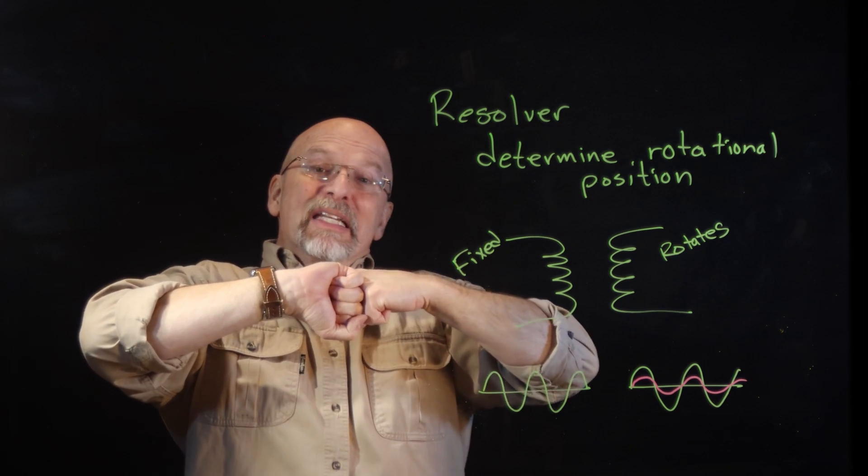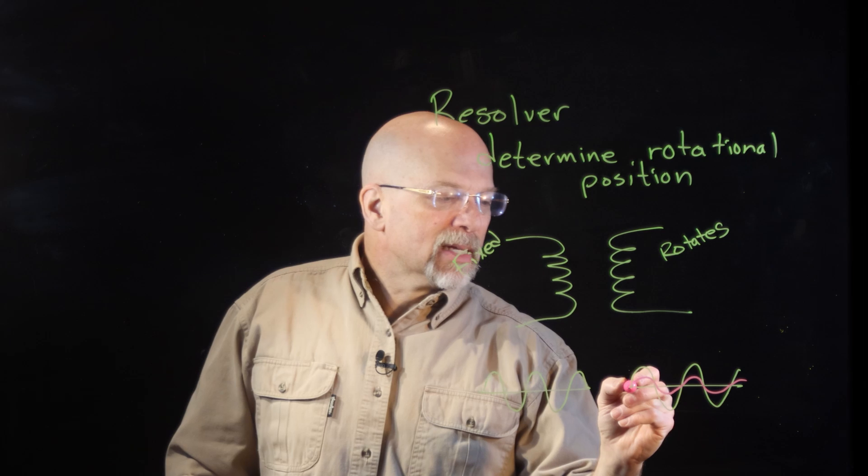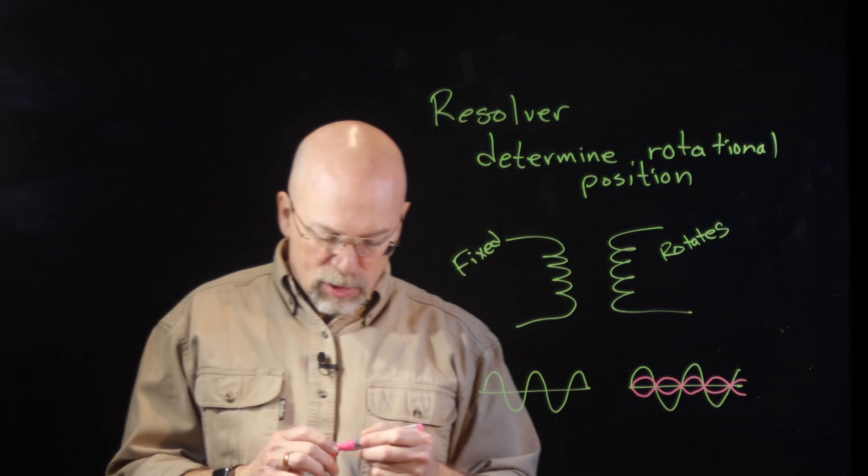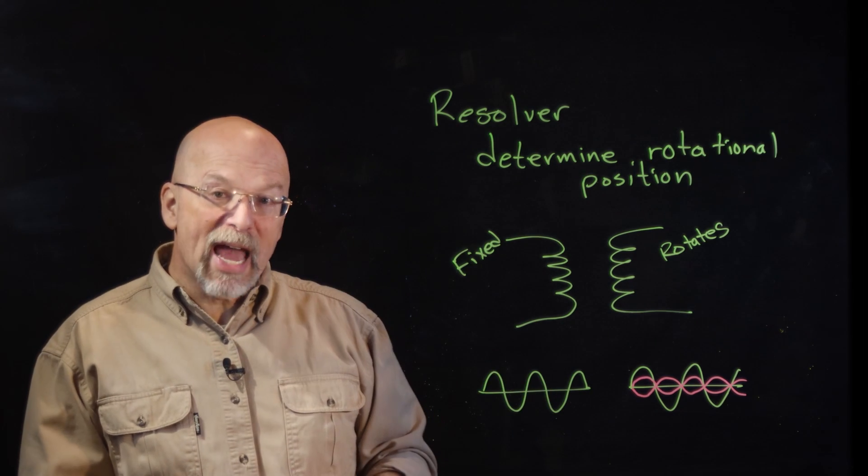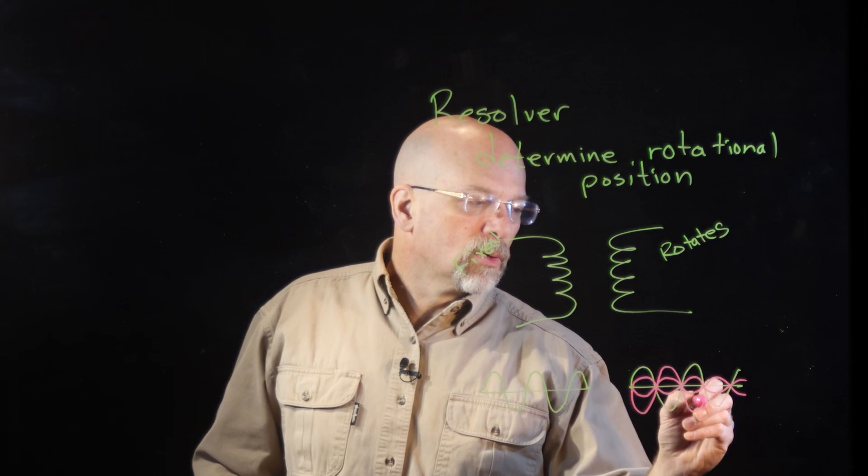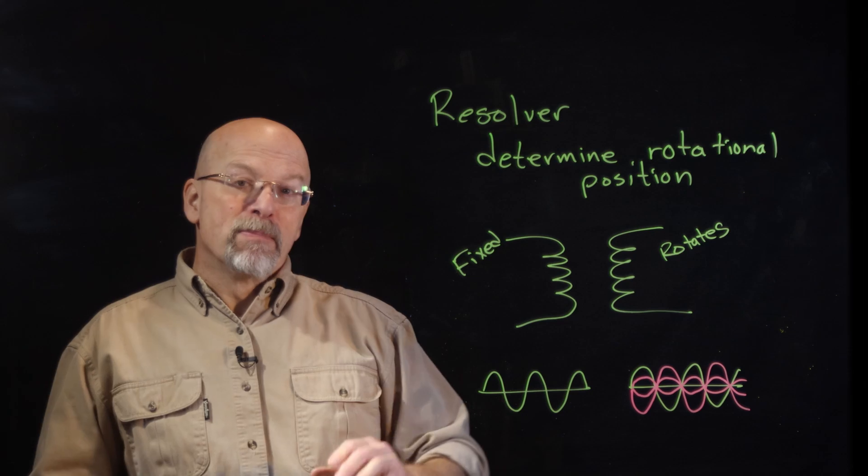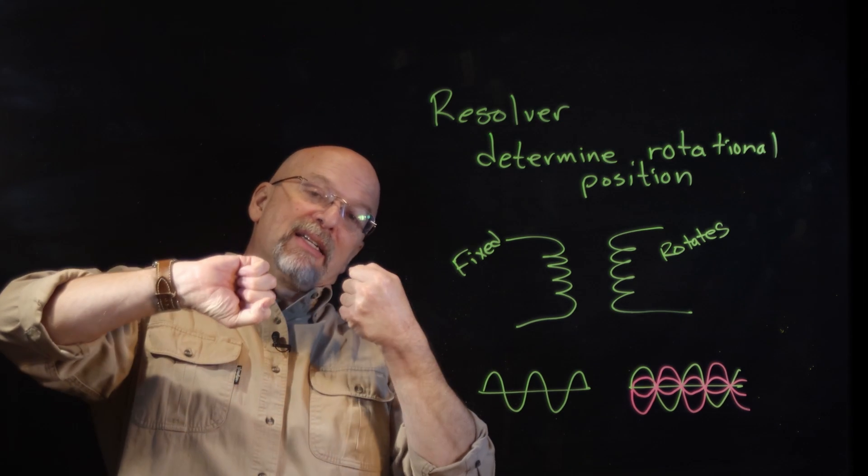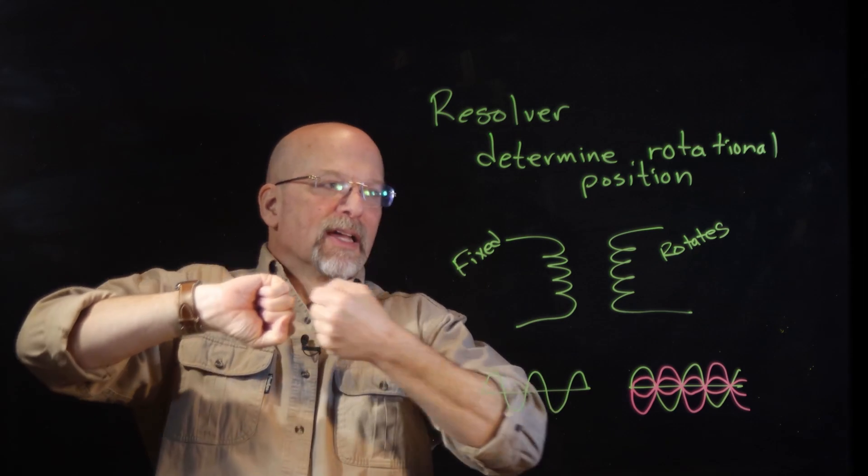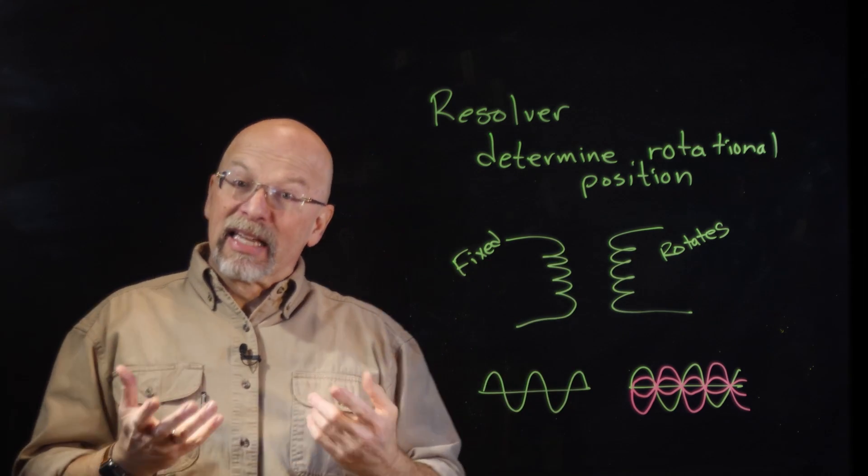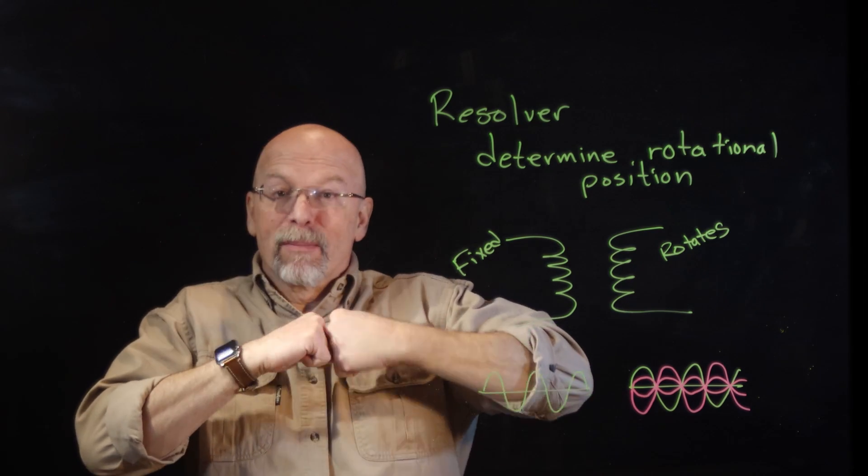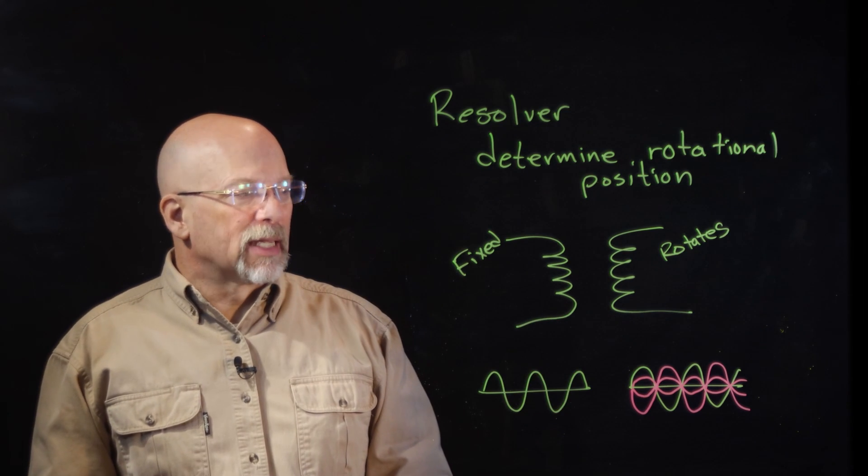Now if you continue to turn, what's going to happen is our frequency is going to stay the same, but the amplitude is going to flip, it's going to go negative. And in fact, when we get to a point where the amplitude is back to the maximum amplitude, but it's 180 degrees out of phase, that means that the fixed coil is 180 degrees out of phase with the rotated coil. Gives you the ability to identify the position of a rotating shaft.